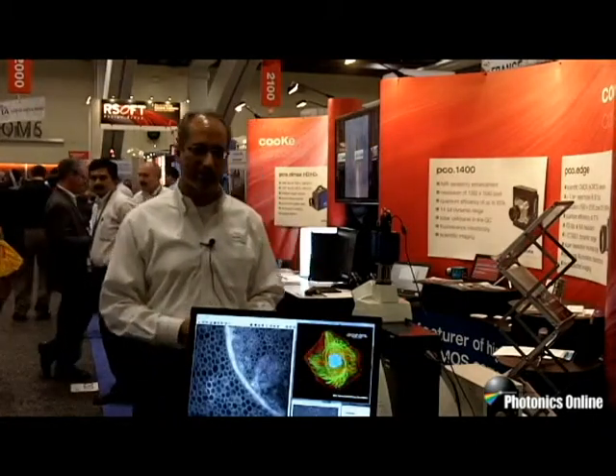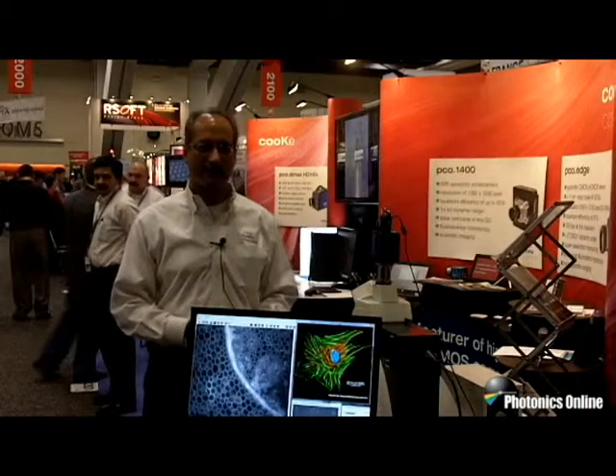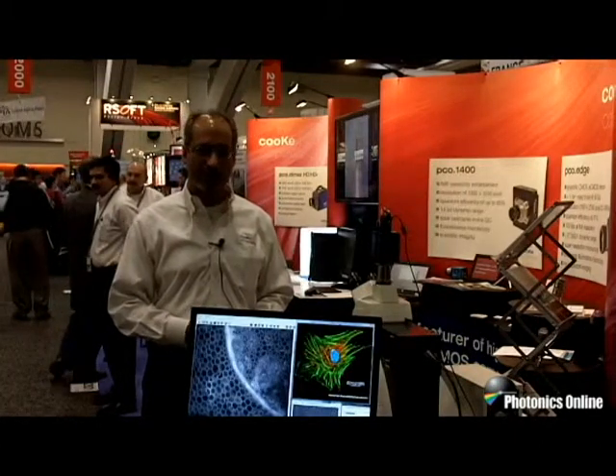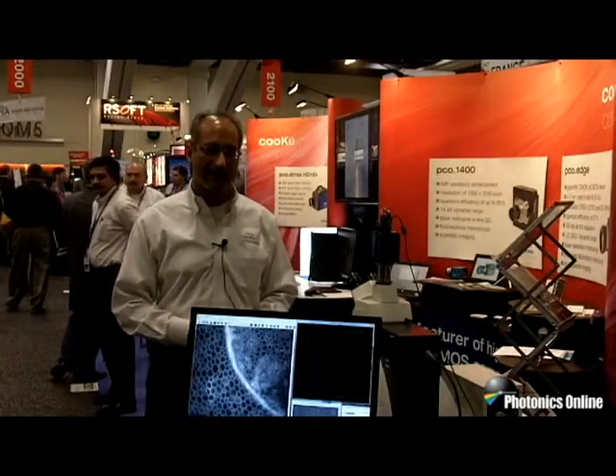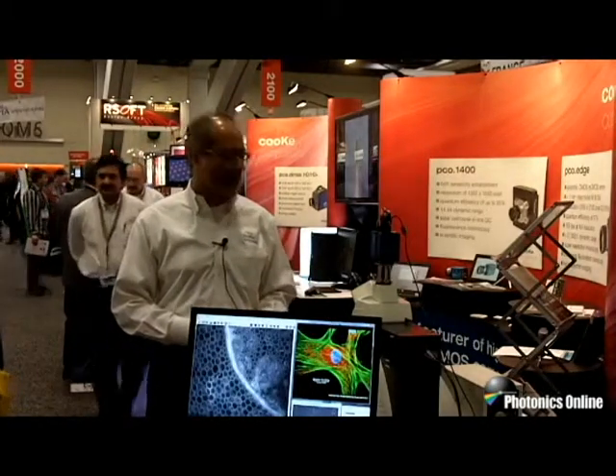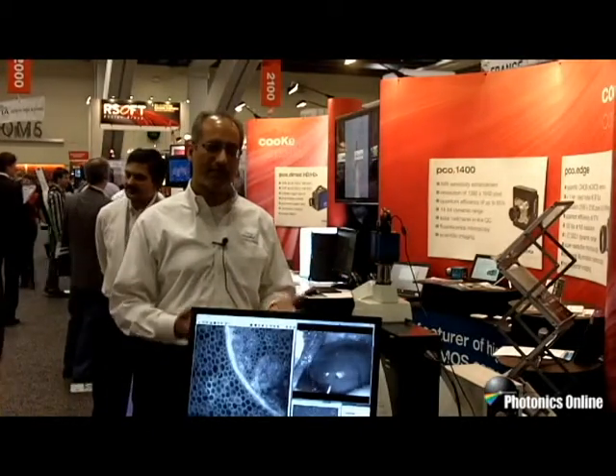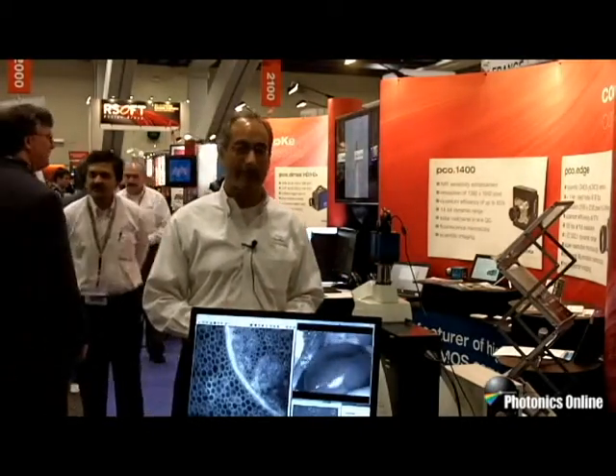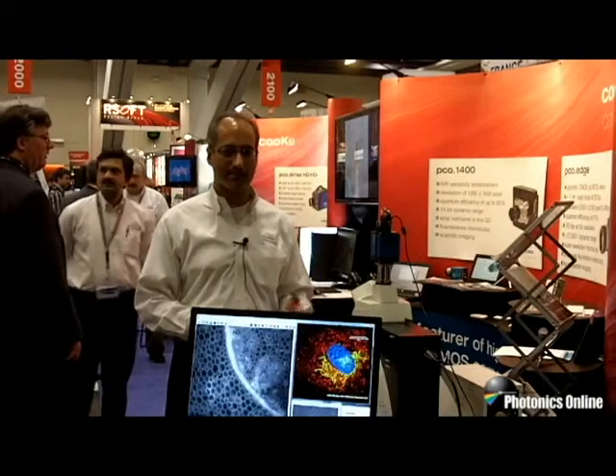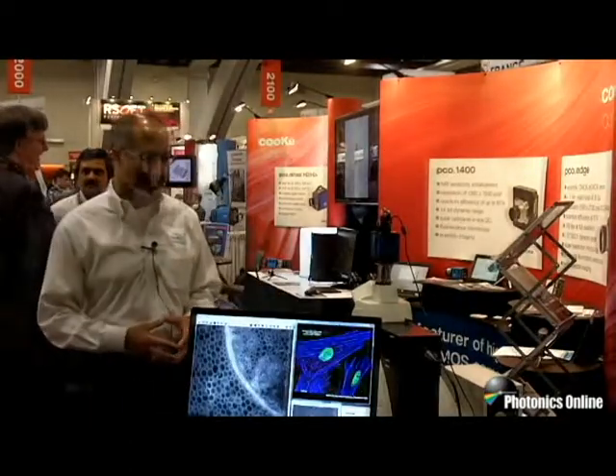Specifically, it has 5.5 megapixels of resolution. It also has down to about one electron of read noise. And we can image 5.5 megapixels at 100 frames per second. It also allows for a 30,000 to one dynamic range — quite exceptional — and we have a 16-bit digitizer to take advantage of that.